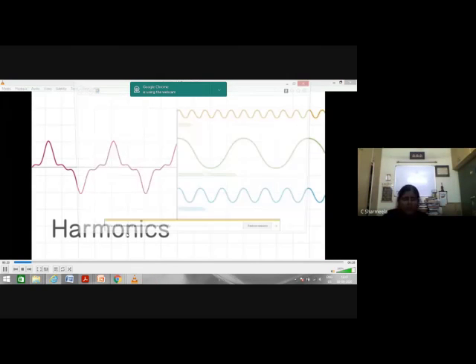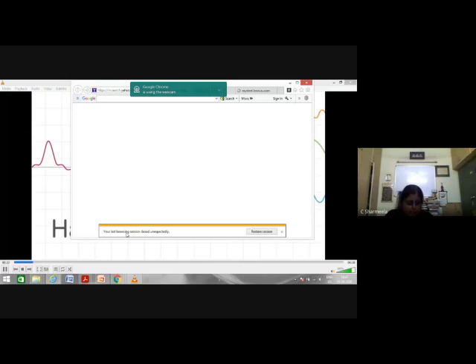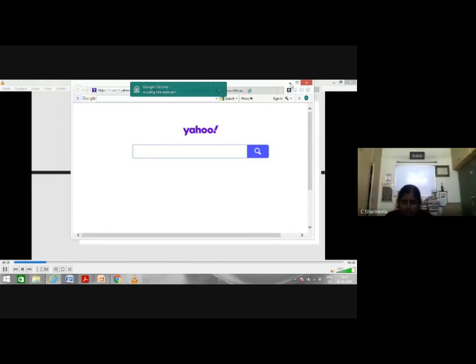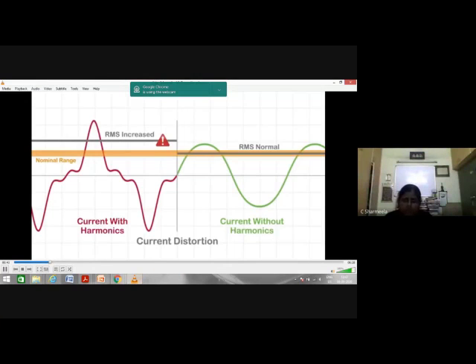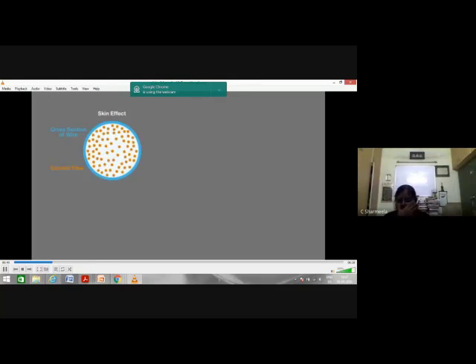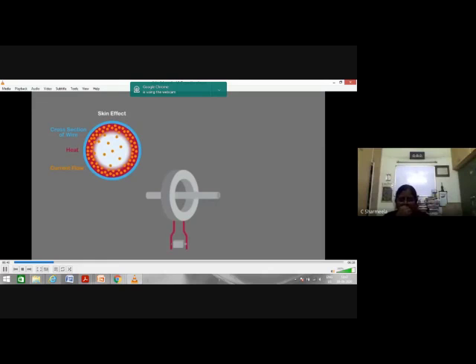Harmonics are high-frequency current and voltage. These stress the electrical distribution network, being that most electrical distribution networks are a stiff or low impedance system. Voltage distortion can cause distortion of control signals and stress electrical equipment's dielectric material. Current distortion increases the electrical distribution network RMS current that can cause skin effect on a conductor, overload transformers, and nuisance tripping of circuit breakers.